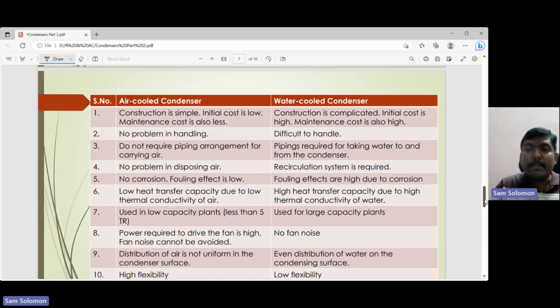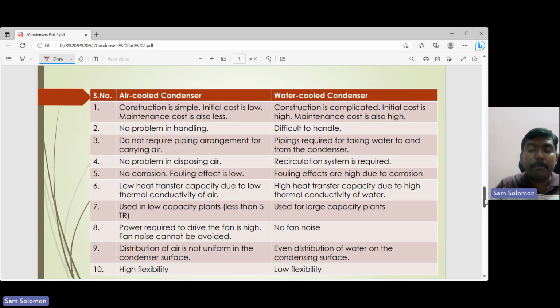And you can see the difference between the air-cooled condenser and the water-cooled condenser as mentioned by Khurmi in his textbook. So the construction is simple in case of the air-cooled condenser, so the initial cost is going to be low and the maintenance cost is also less. Whereas here the construction is a little bit complicated, and because the construction is complicated, you're going to have a higher initial cost and the maintenance cost is also going to be high. There is no problem in handling the air-cooled condenser, but it is a little bit difficult to handle here, and the maintenance is also a little bit difficult.